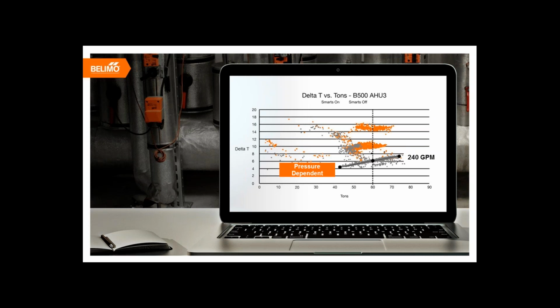valve. Basically, we were able to turn the functionality of the Energy Valve off, including the delta T manager and the flow control technology, to make the valve behave as a regular pressure-dependent control valve. The only functionality enabled was the modulating control function. When we ran the valve, we were able to maintain a 60-ton load through the unit at an average flow of 240 GPM.